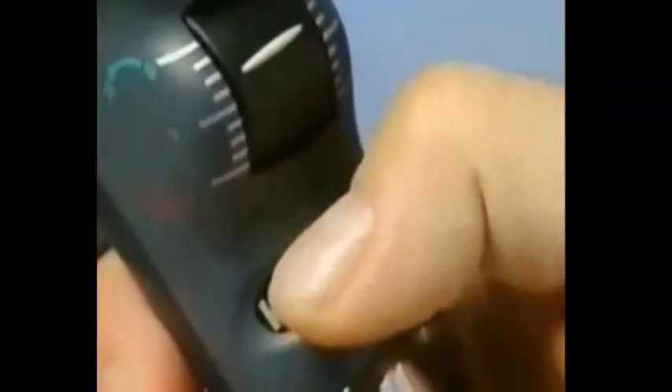Just below the focusing wheel, the aperture dial allows you to select the apertures or filters you may need. Spot sizes include micro, small, and large. Panoptic model 11810 also contains a slit aperture for seeing elevation changes and a red-free filter for higher contrast resolution, giving you a better ability to distinguish between blood vessels and hemorrhaging lesions. It also includes a half-moon aperture, which provides a combination of depth perception and field of view.